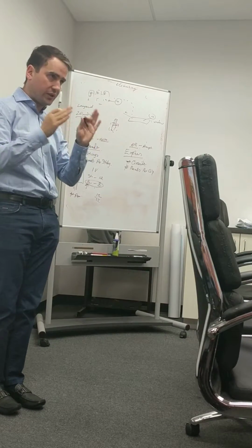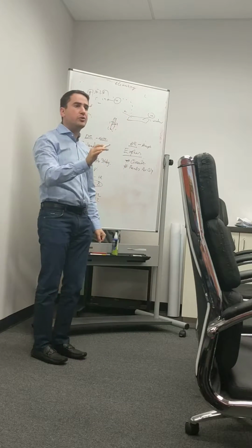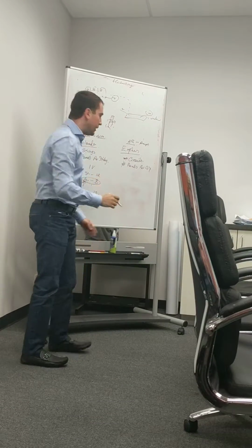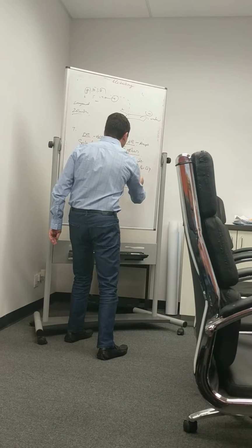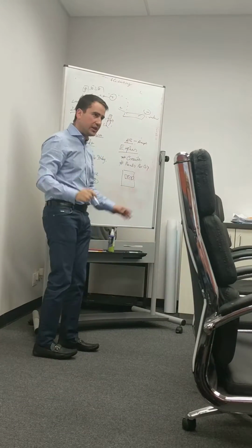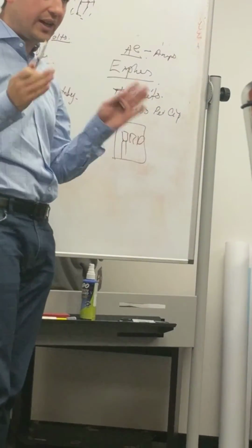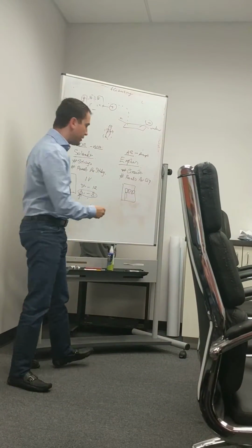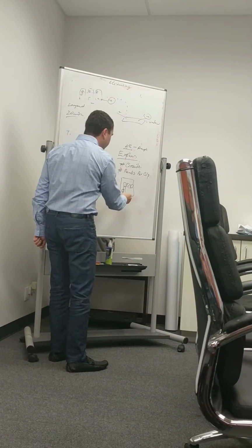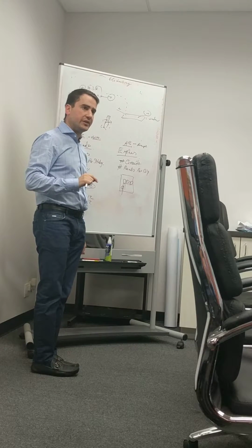So basically when you find this out, you know which string, and you chase that string, MC4 connectors or optimizers, okay? Now, when you have Enphase microinverters, how do you do this the easy way? You have a combiner box, right? You have this sub panel with the breakers, 1, 2, maximum 3, correct? It has line 1 and line 2, it doesn't have strings. You put your clamp amp meter. How many amps is per microinverter?